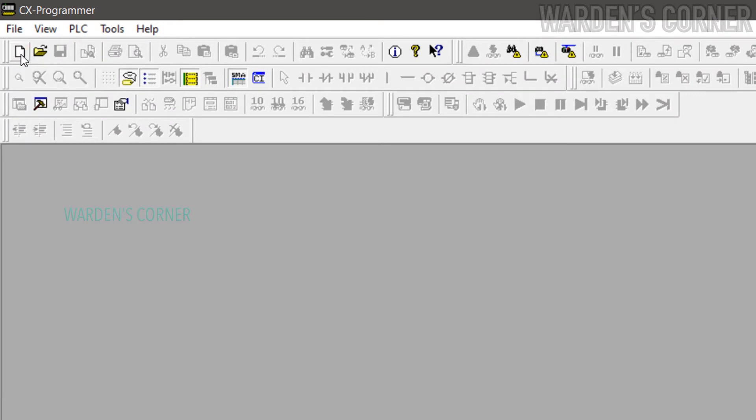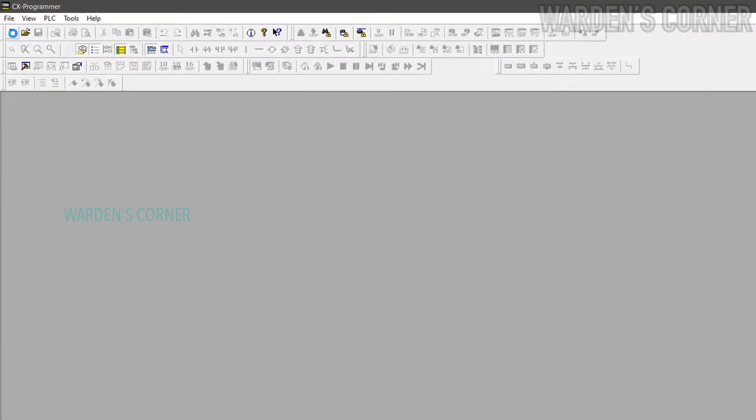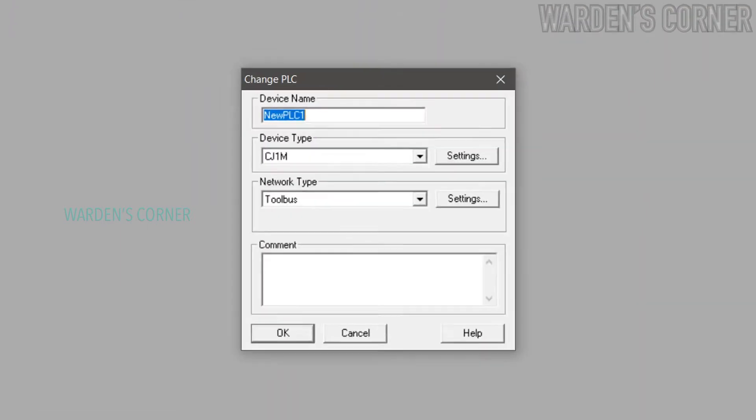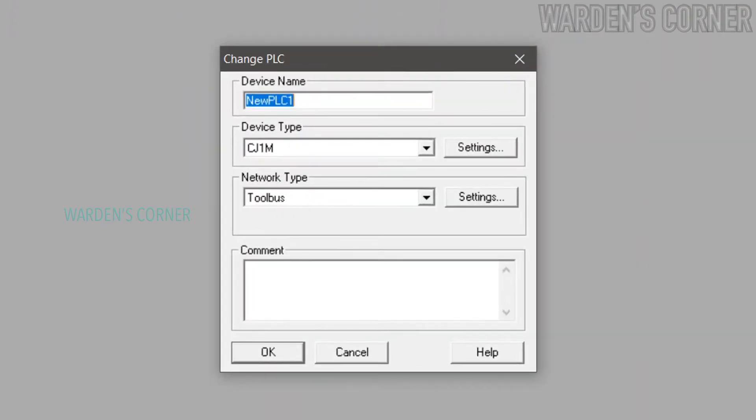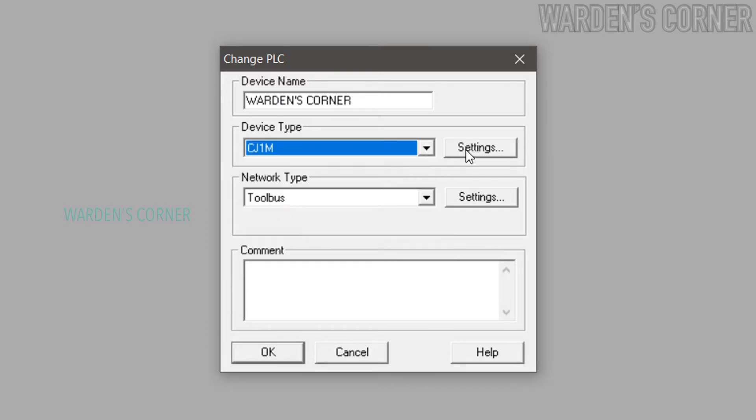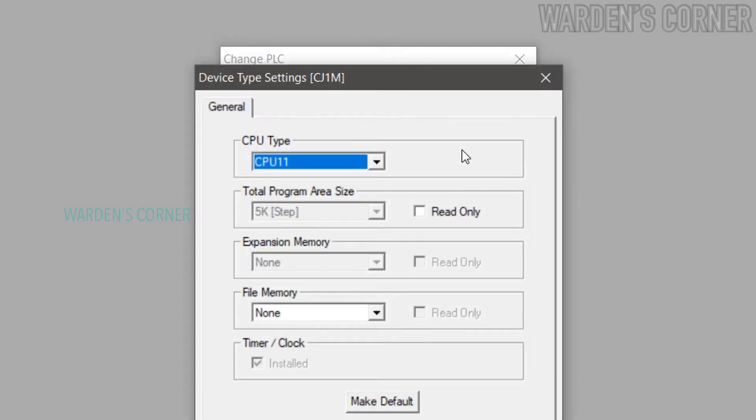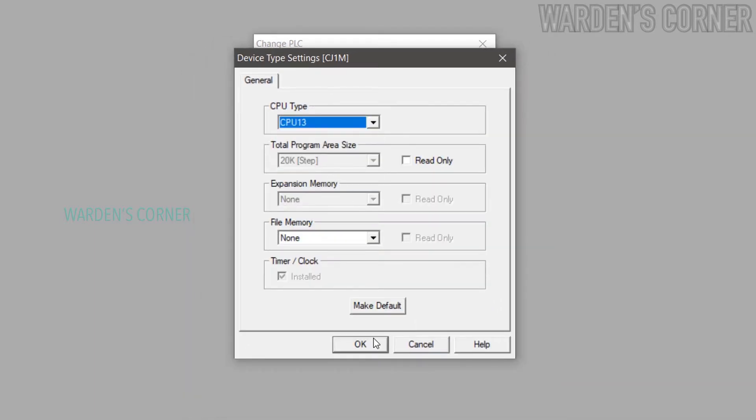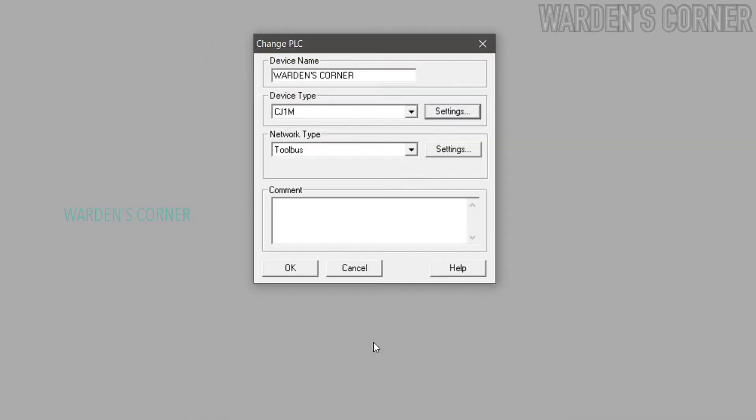Click New icon or press Ctrl+N. A new tab will appear. Here it is where you can select your PLC type. You may type your device name. Select Device Type: CJ1M. Click Settings, select the CPU type: CPU13. That is the actual CPU model of the PLC unit.